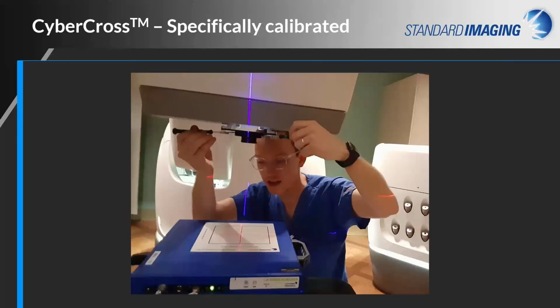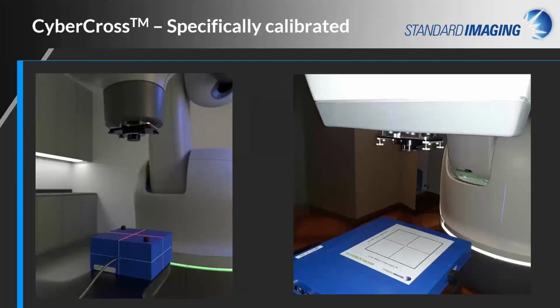Here, our QA StereoChecker alignment markings are used to adjust the device crosshair shape and location. Once calibration is completed, it can be used anytime a crosshair is needed. It is easily attached for alignment, then detached for QA procedures, such as delivering QA plans for analysis with, or preferably without, film.